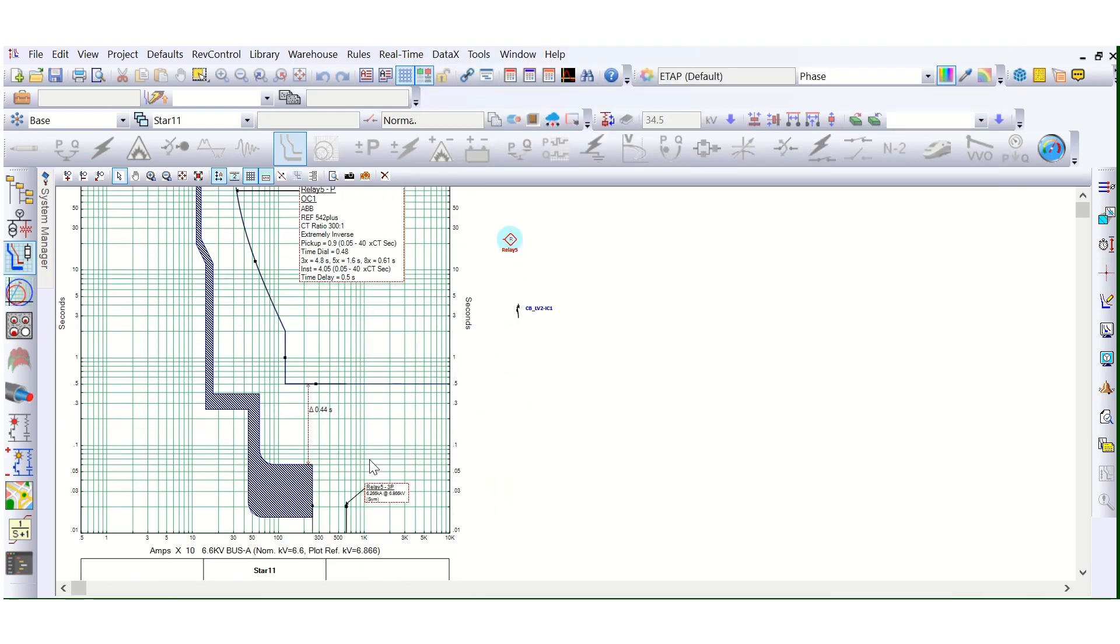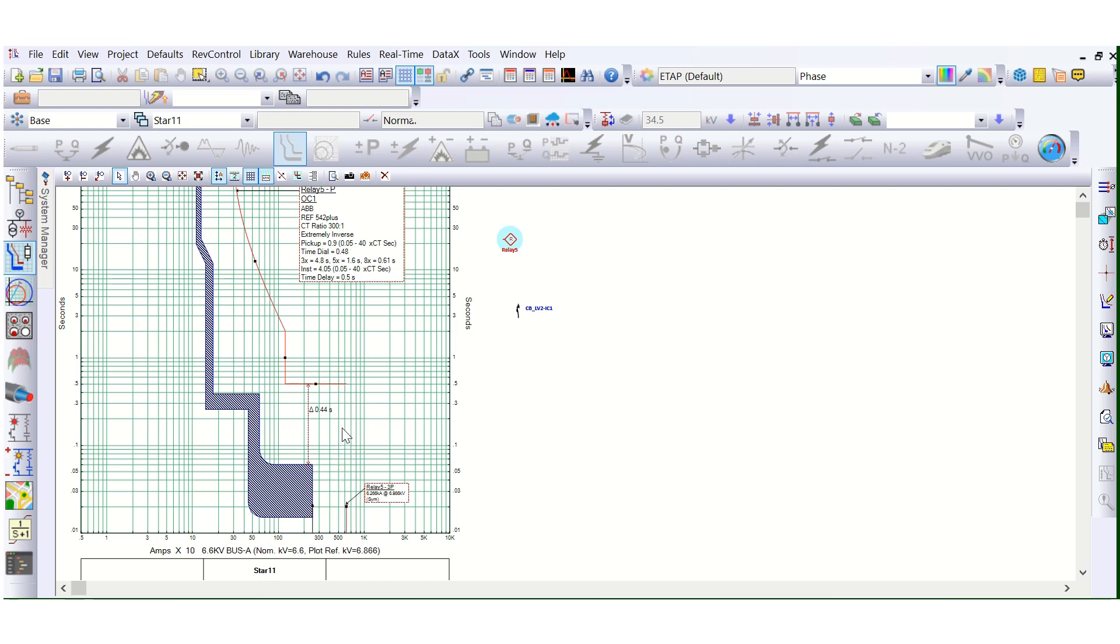Now if I want to do better coordination and if it is required, let's say this Stage 3 is required, I want to coordinate this part also. Basically, this is applicable if there is any motor in the downstream. Let's say this is motor, so this motor starting curve will be like this. So in that case, we can use 3-4 stages for better coordination purpose.